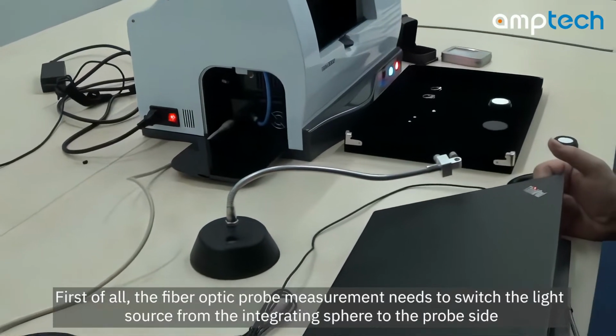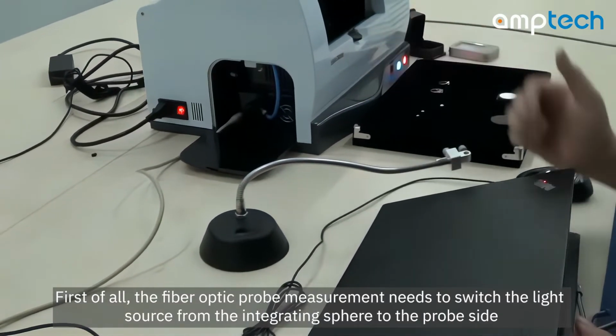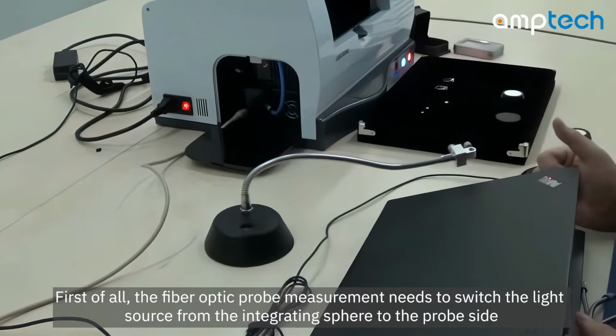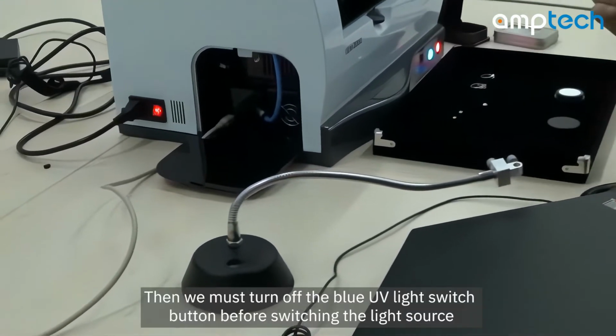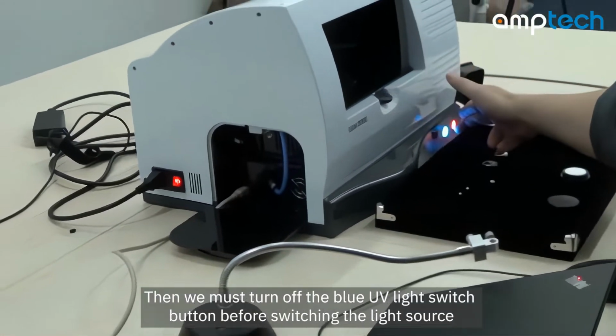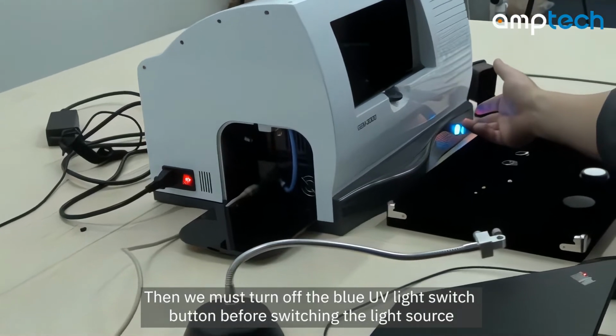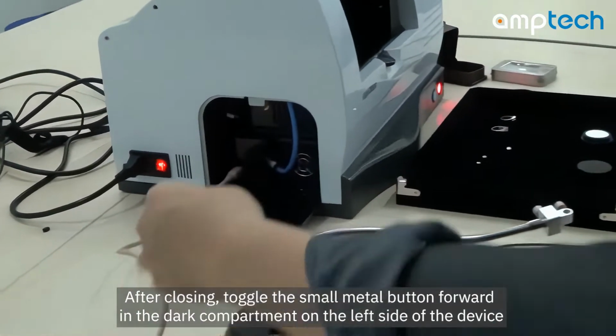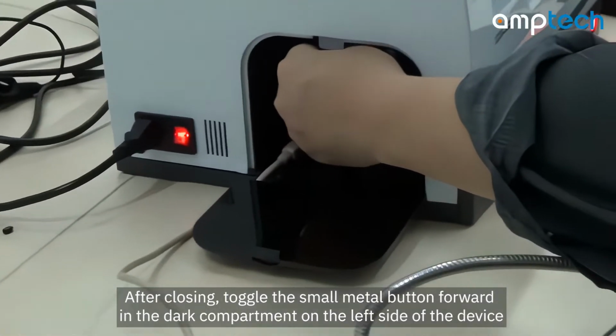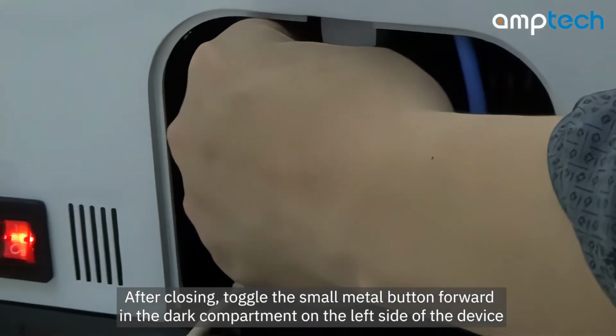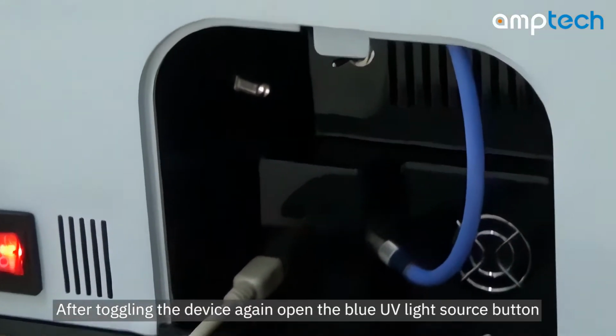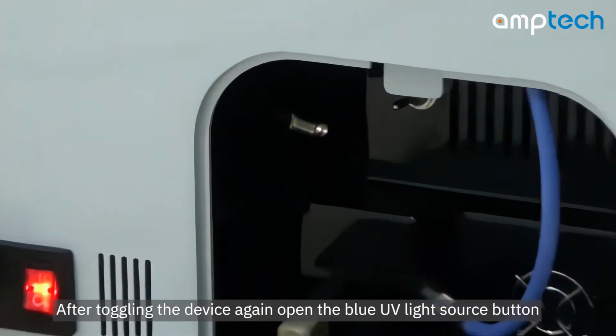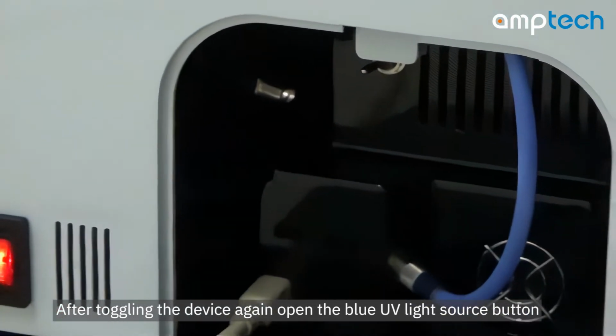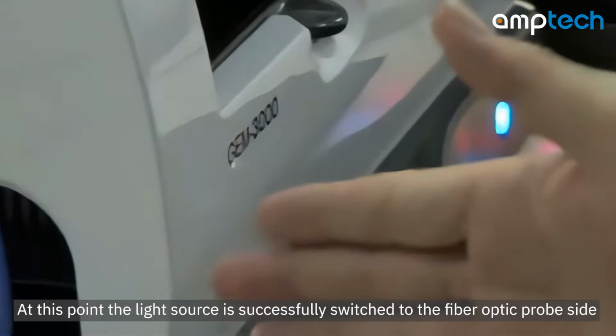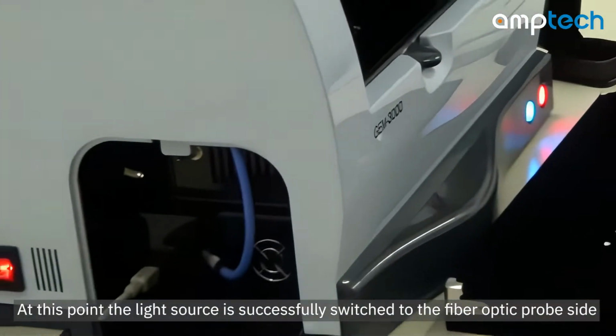First of all, the fiber optic probe measurement needs to switch the light source from the integrating sphere to the probe side. Then we must turn off the blue UV light switch button before switching the light source. After closing, toggle the small metal button forward in the dark compartment on the left side of the device. After toggling the button, open the blue UV light source button again. At this point the light source is successfully switched to the fiber optic probe side.